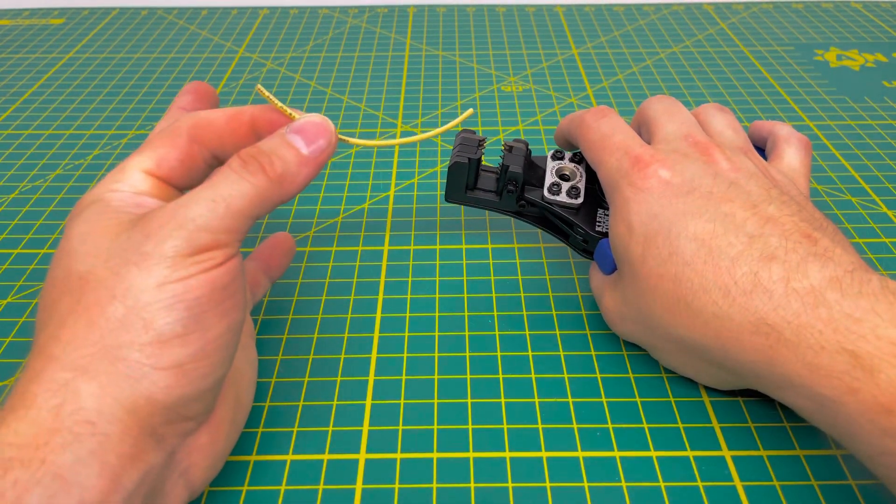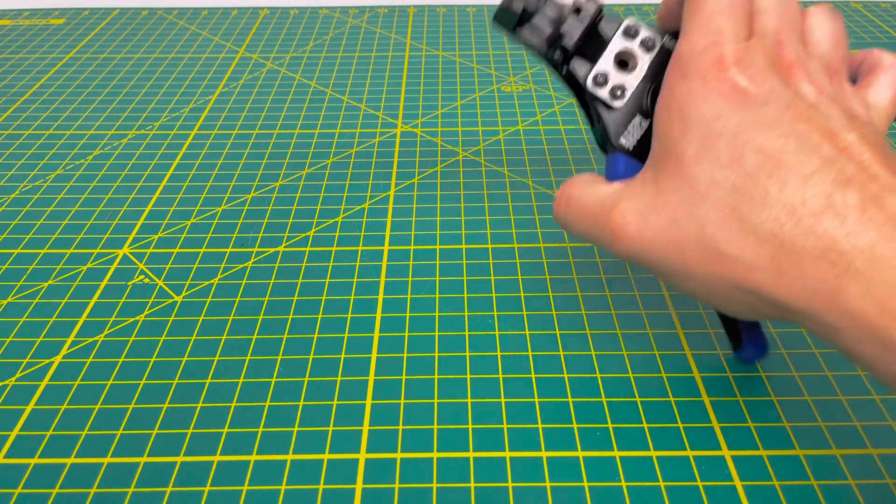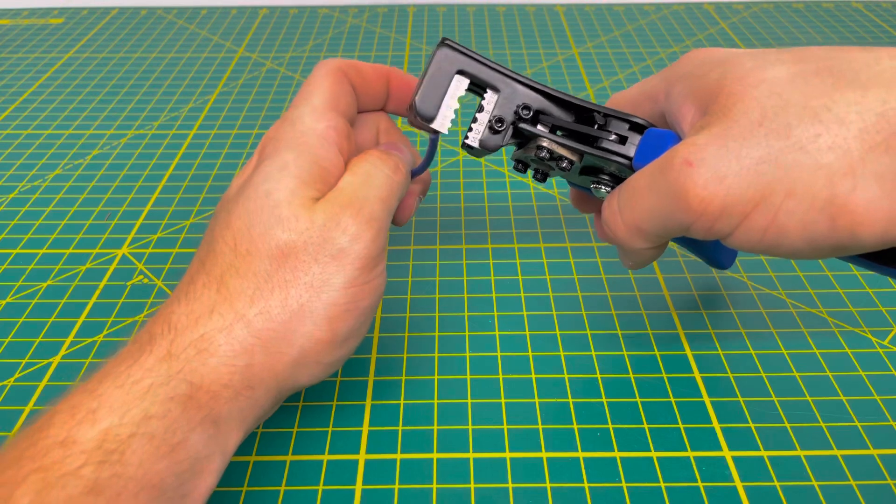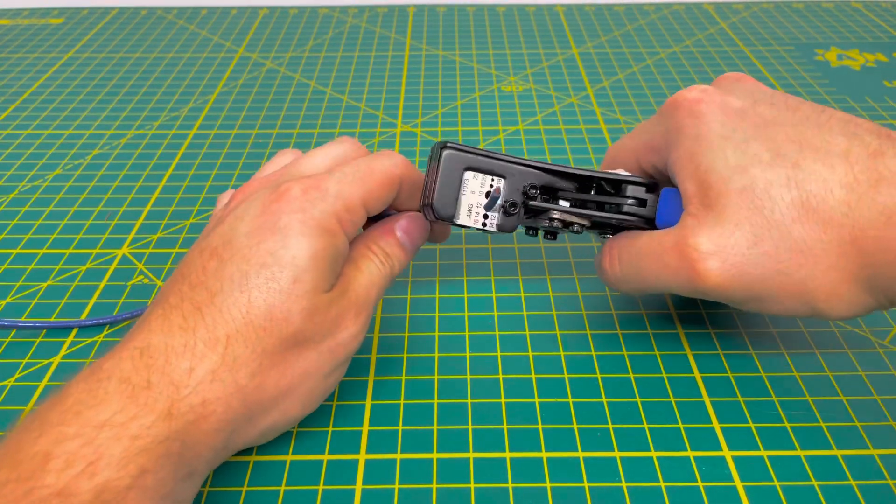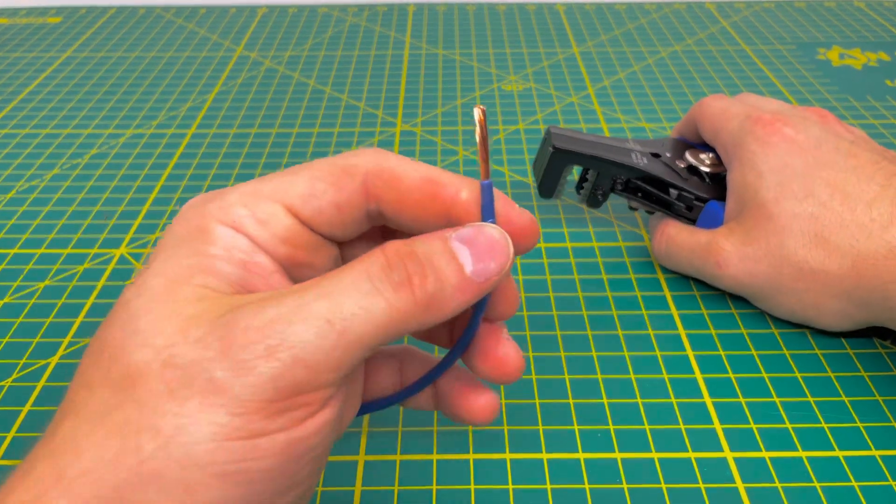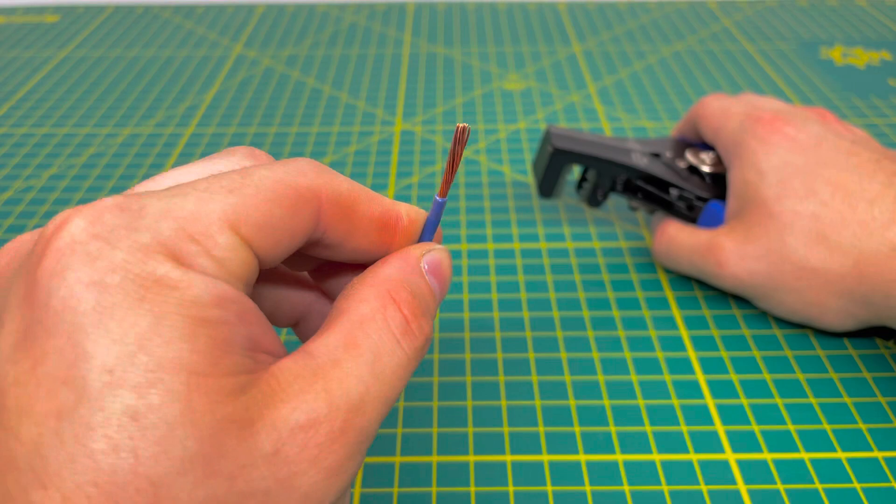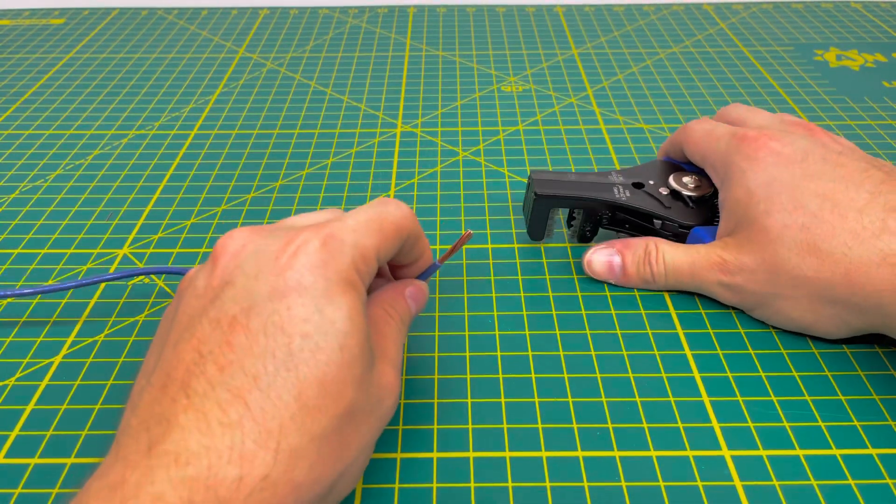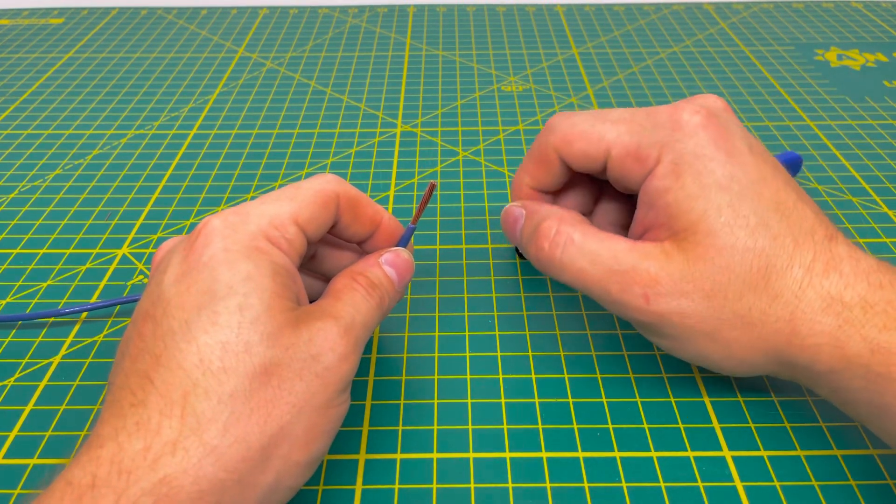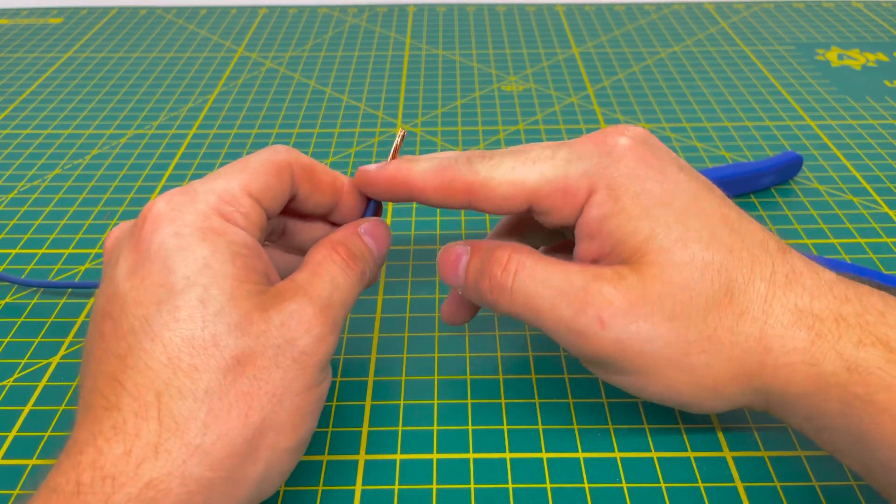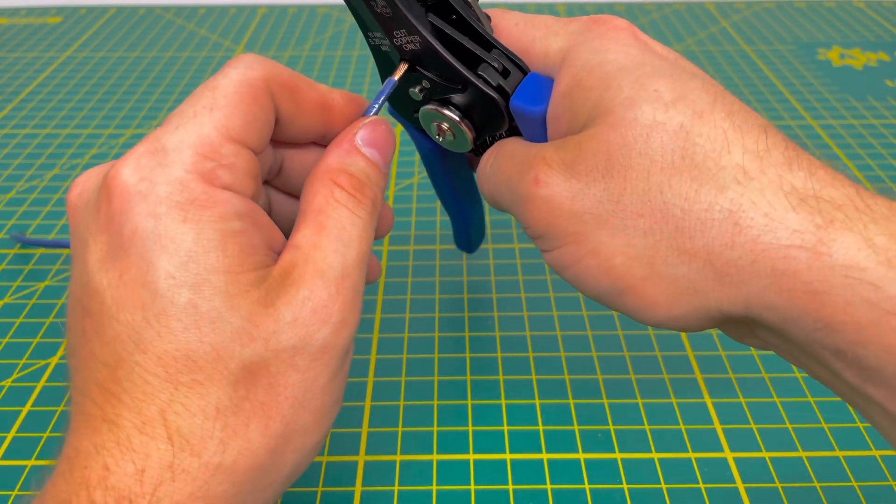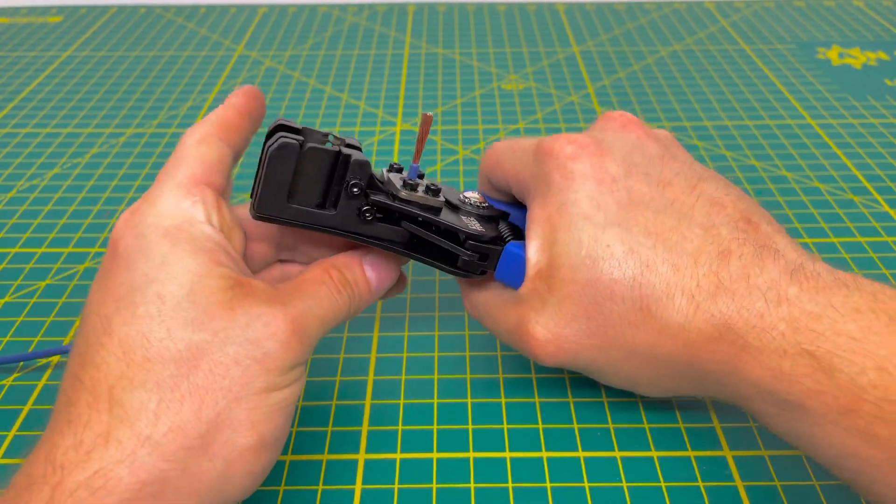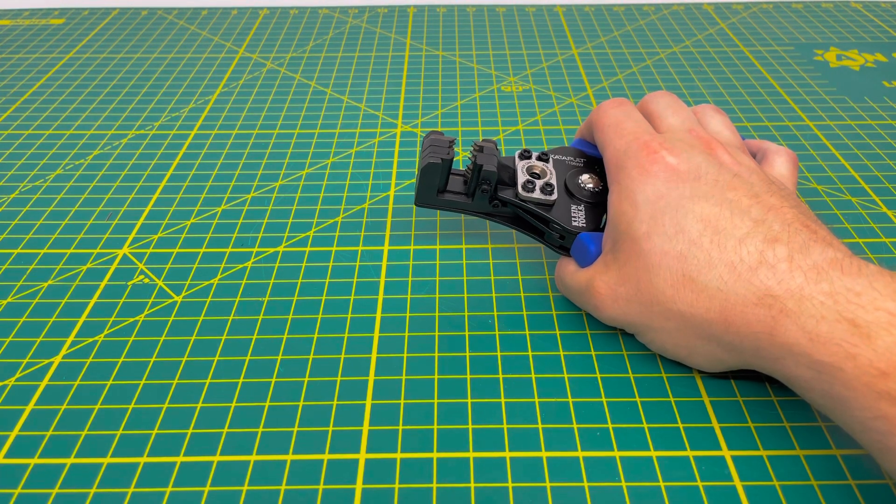That was with the 18-gauge stranded wire. I'll go ahead and bring in some 12-gauge stranded wire and give it a little bit better of a demonstration. I'll go ahead and line that up with the correct size hole. And you are able to strip it fairly easy, which is nice. And again, no damage done to the wire. It's a pretty clean strip overall, whereas sometimes with the regular pair of wire strippers, you kind of can tear some of the insulation if you don't press down hard enough to cut that insulation all the way around. That is one nice thing about these automatic wire strippers. And there again, super easy to cut through that conductor right there.